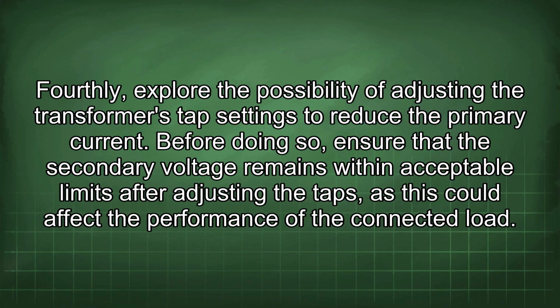Fourthly, explore the possibility of adjusting the transformer's tap settings to reduce the primary current. Before doing so, ensure that the secondary voltage remains within acceptable limits after adjusting the taps, as this could affect the performance of the connected load.